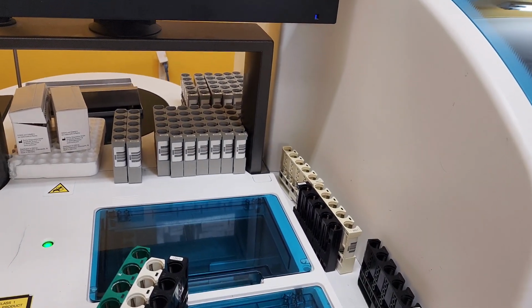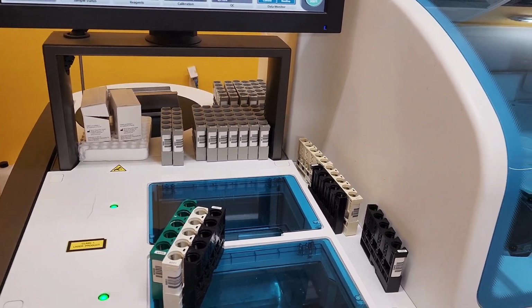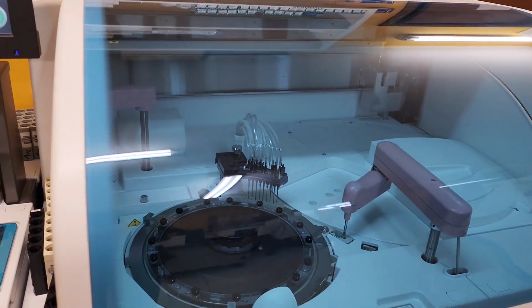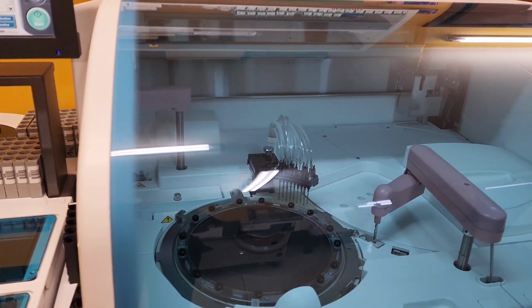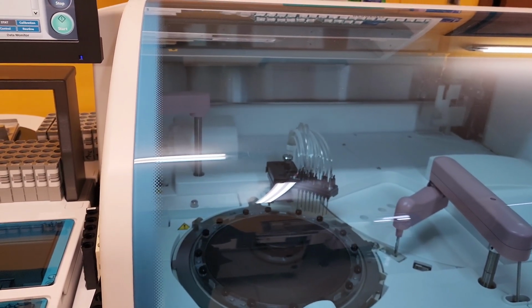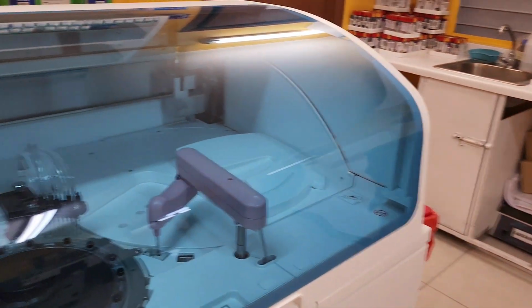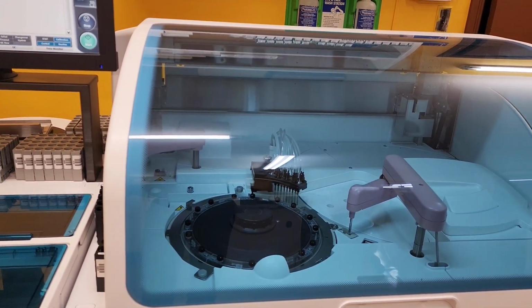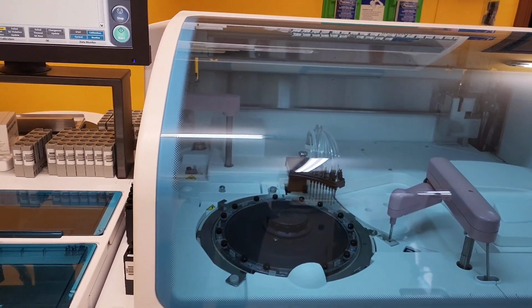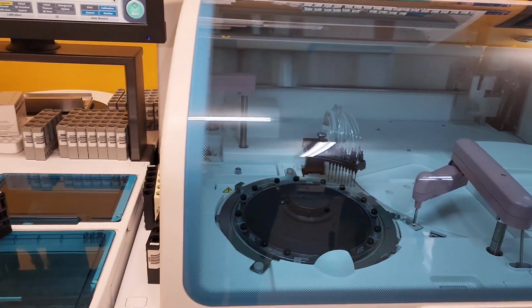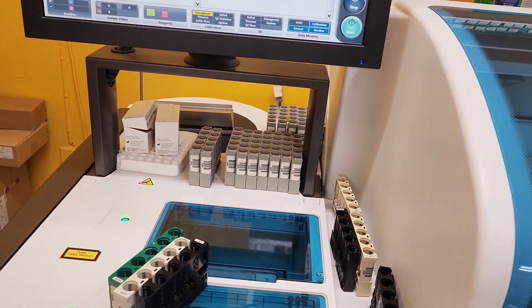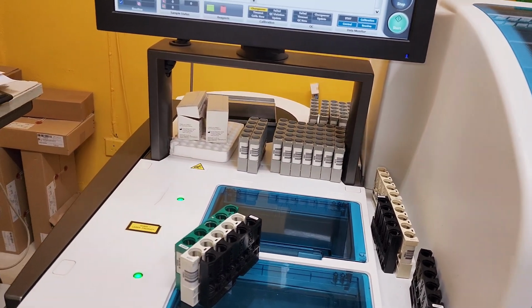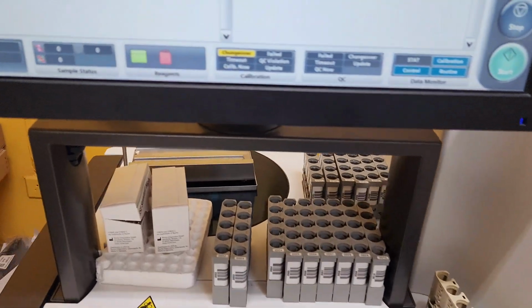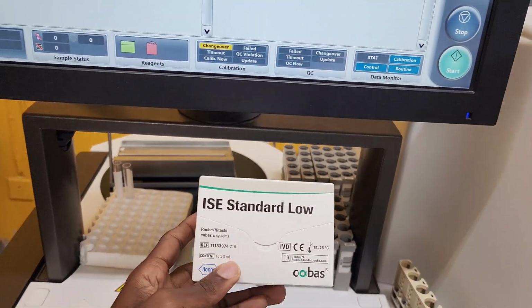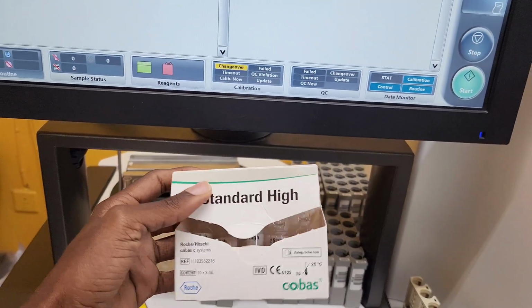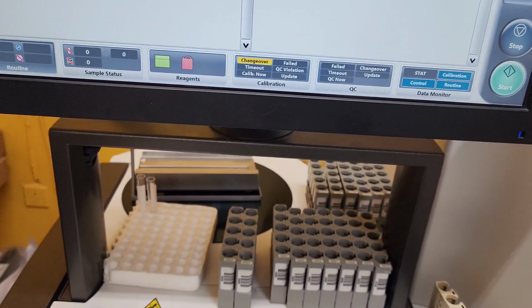So we have to run calibrations and controls daily before we start the day's work. If the controls or the calibrations don't come in, then we have to repeat them before we can go ahead, because we want to ensure that we are giving out accurate results or a true representation of what is going on with the patient's sample. So the calibrations will have to be done daily, and the controls also. So for the beginning of each shift, we have to run those. So yeah, these are the calibrators for the ISE. So that's the sodium, potassium, chloride.